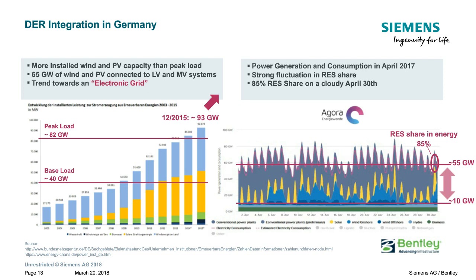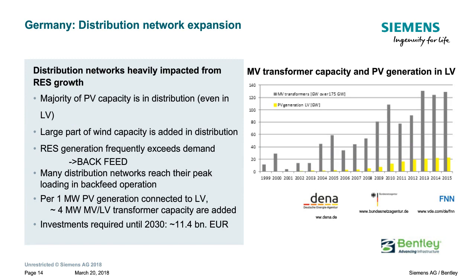This slide refers to distribution network expansion due to DER penetration. If we have more PV interconnected to the grid at noon when residential customers have low peak, and back-feed to the network exceeds transformer capacity, investment is required. This slide shows that the investment required until 2030 is around 11.4 billion euros for distribution network expansion due to DER.